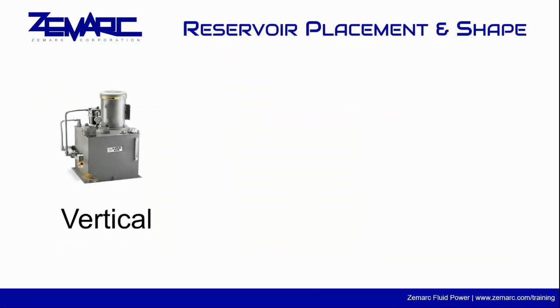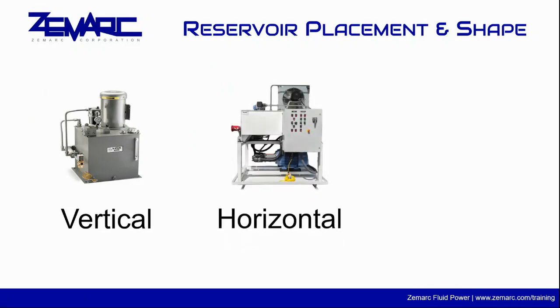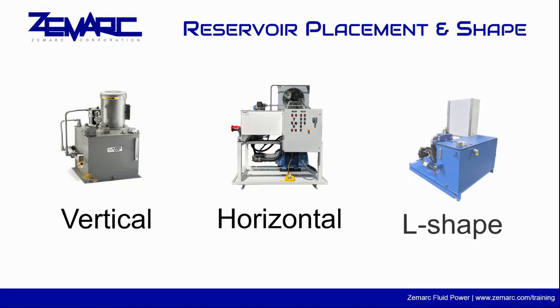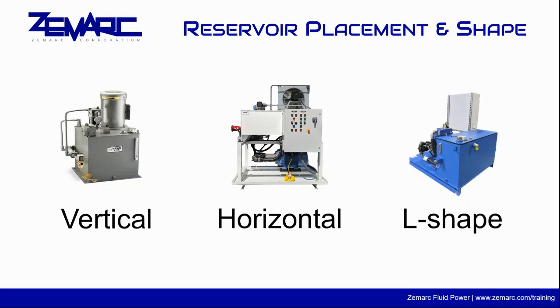There are 3 main types of reservoirs we use. There's vertical reservoirs, where the pump is submerged in the reservoir. These are compact and provide increased cooling and can help prevent cavitation. Horizontal reservoirs have a simple design which allows for specialized mounting, such as overhead mounting. And finally, L-shaped reservoirs allow for greater heat dissipation and can provide mounting space for the rest of your system.